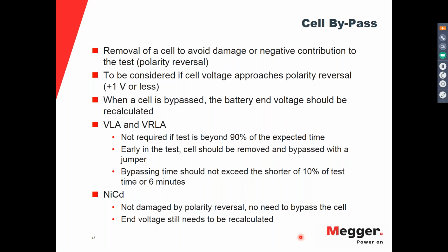So you should be prepared for this. If you suspect that a cell will be failing during the test, you should have a jumper and run this procedure with all the safety precautions to avoid any harm or any damage to the operator or to the technicians, and also to avoid interrupting the test any further, because if not, you're going to have to start again from the beginning, including all the preparation time.